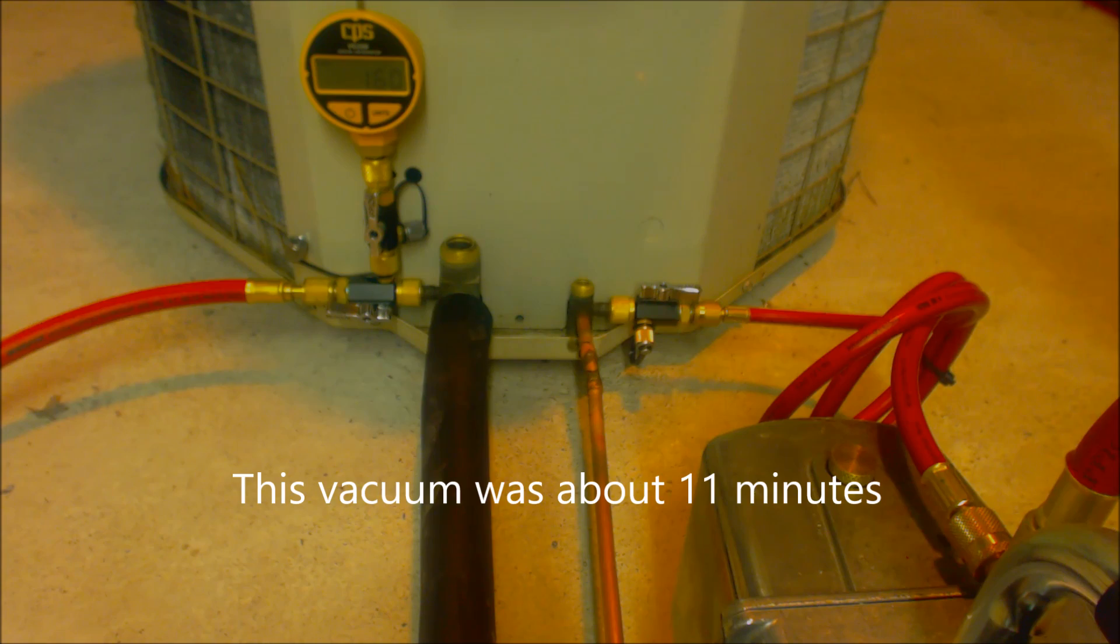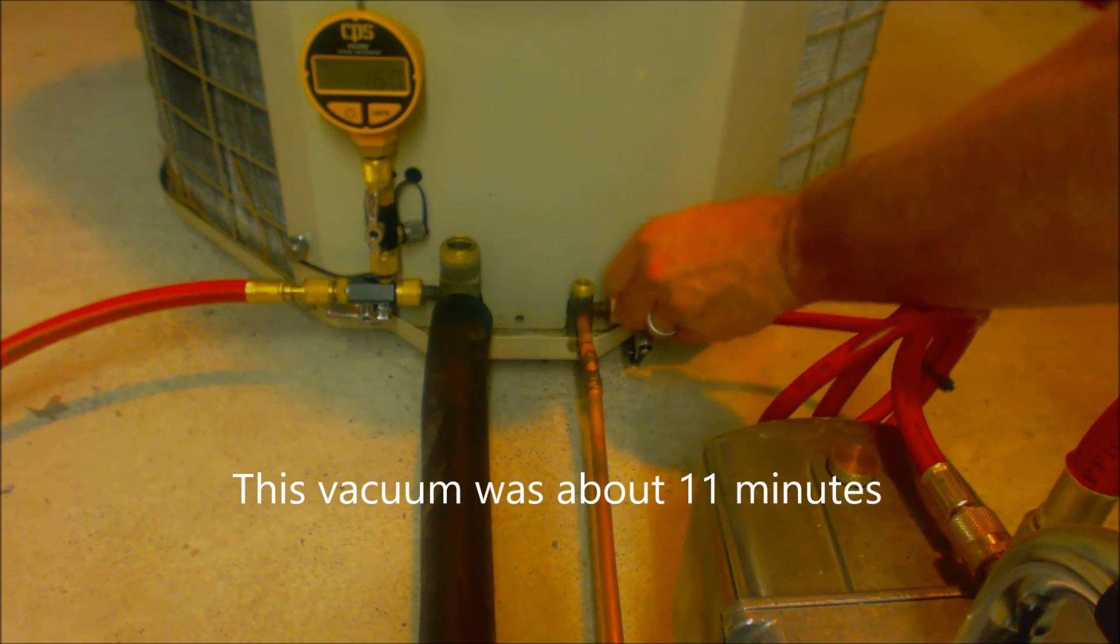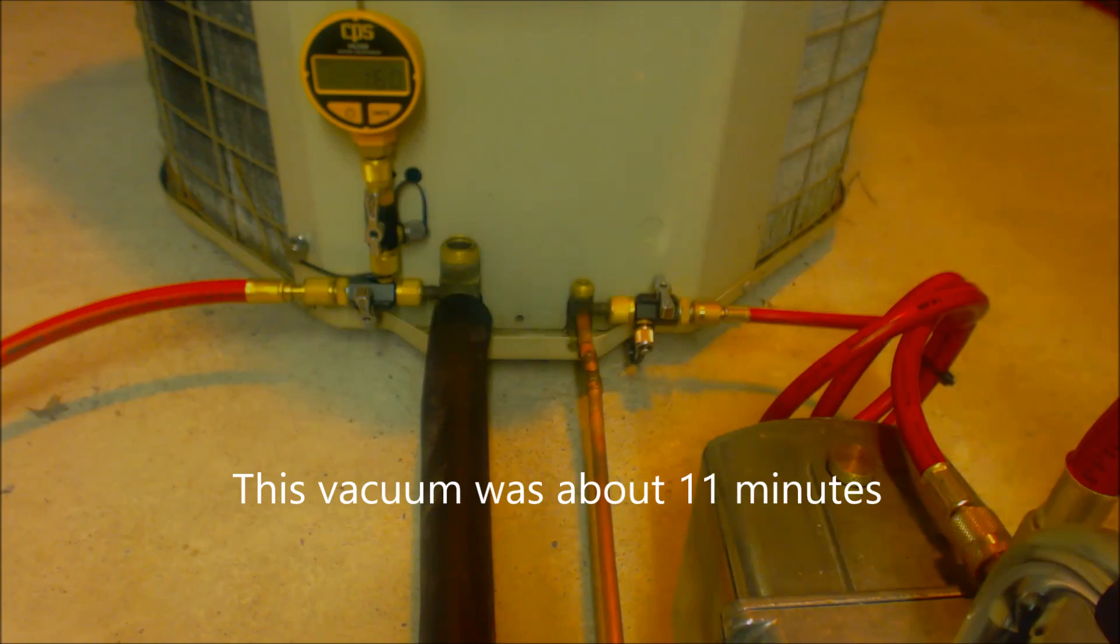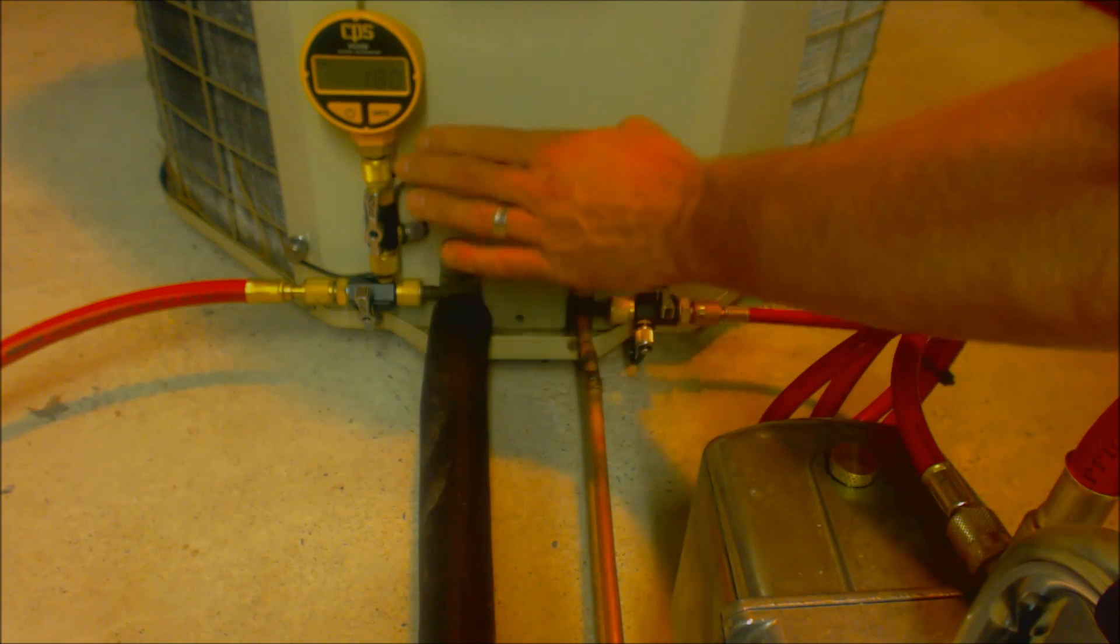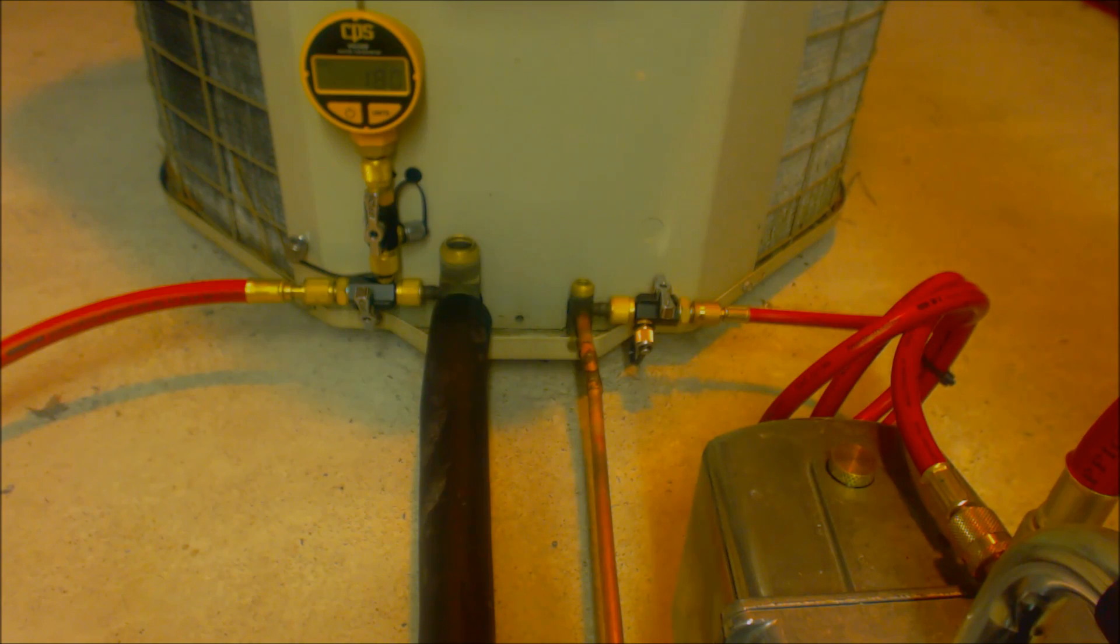Okay, so now we're going to shut the valve cores off and turn the pump off. Now we're going to watch the micron level to see if it rises. What we just did is we turned off the valve cores and we isolated the hose and the vacuum pump from the line set and micron gauge. We're going to let this sit for a little bit and just watch the micron level and make sure it does not rise above 500 microns. If it rises above 500 microns, then we know that we either have moisture in the system or there's a leak.